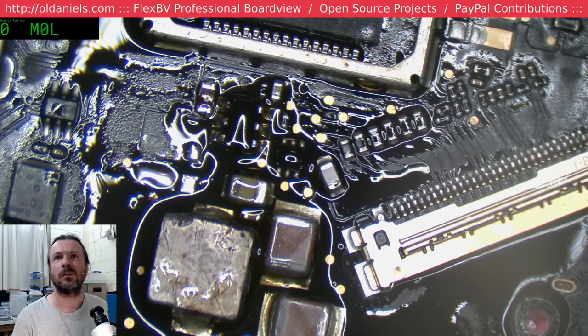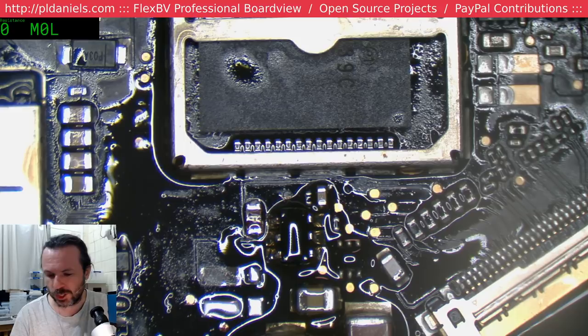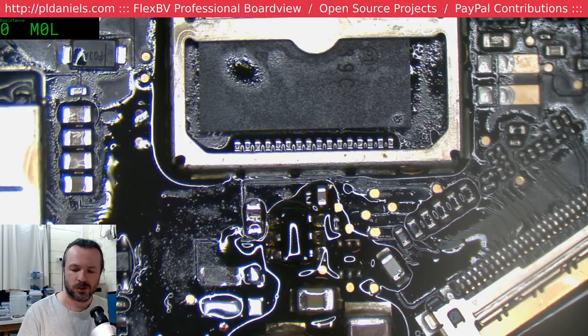Hey, Dragon, good to see you. Christensen, the P is a rating. It's just an easy way to identify what level the fuse is, whether it's 1 amp, 2 amp, 500 milliamps, whatever. So you have all your different letters from A through to Z, roughly. And each letter represents a particular current trip rating.